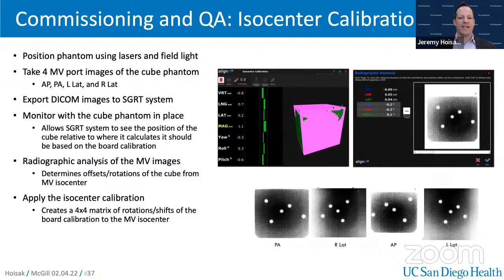We can then image that phantom with the SGRT system, and then take, in this case, MV port images at four different angles, and then do a radiographic analysis, and that can provide an isocentre calibration for the linear accelerator's isocentre and the SGRT system isocentre. This is typically only done monthly or even quarterly.